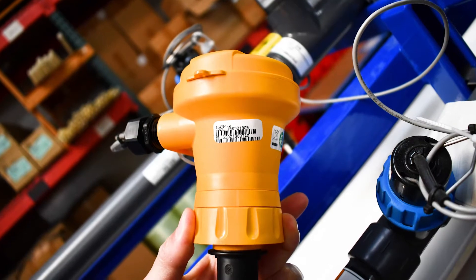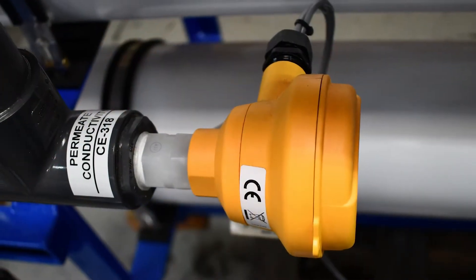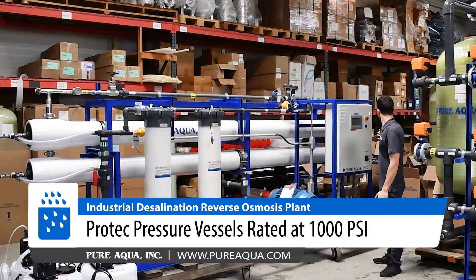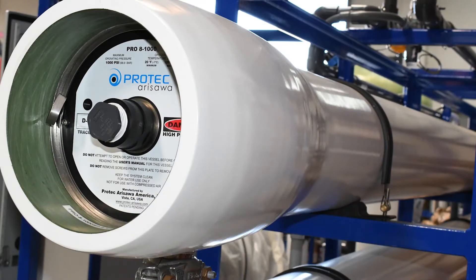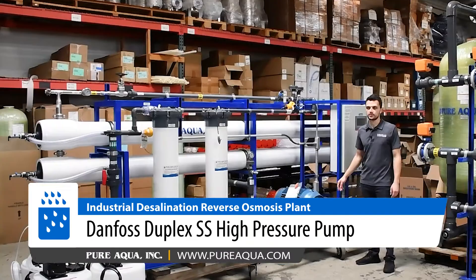We measure the feed ORP before feeding the membranes to ensure that we're always around the 240 millivolt level. We are utilizing the Hydranautics SWC5 LD membranes, which are very good in terms of rejection and offer a balance of energy consumption, sizing, and pressure for the high-pressure pump motor.